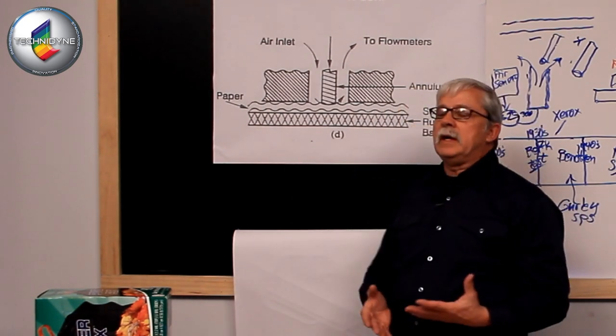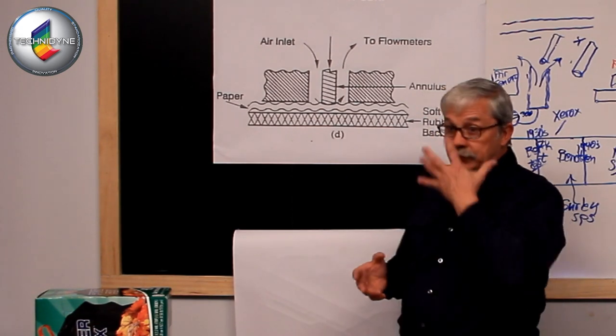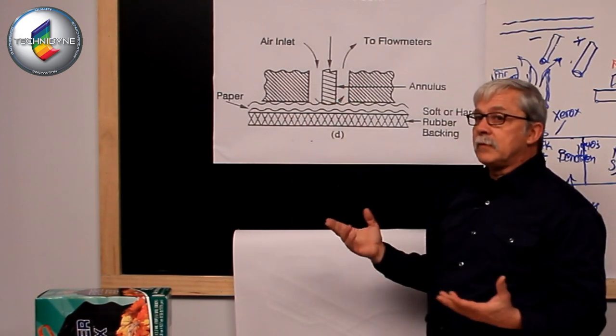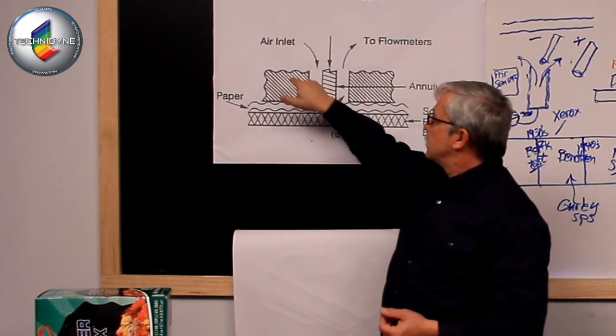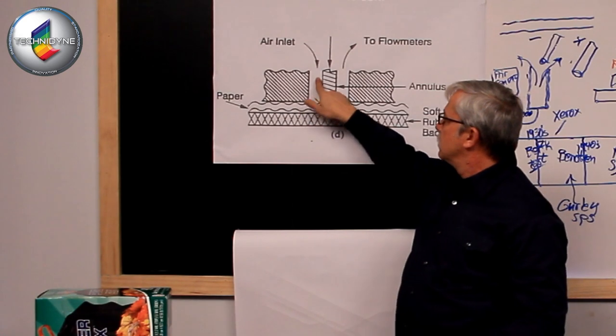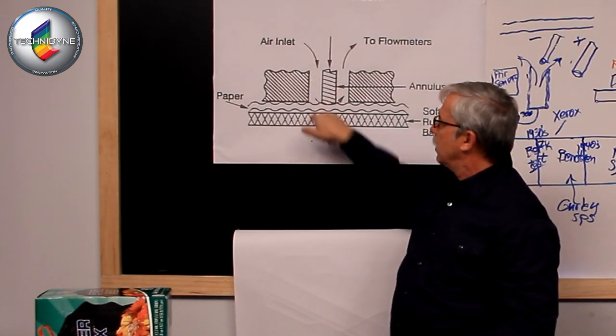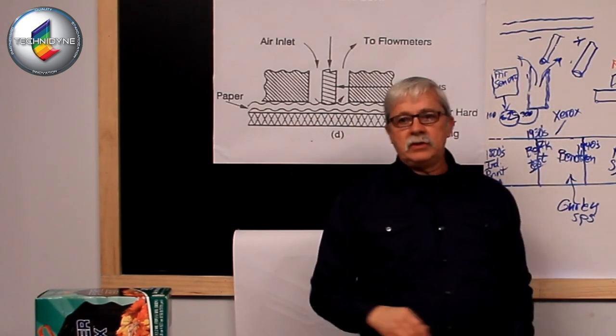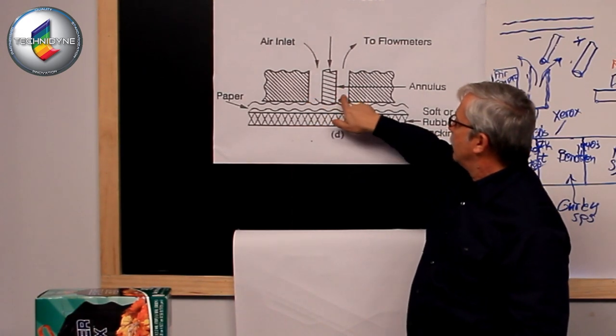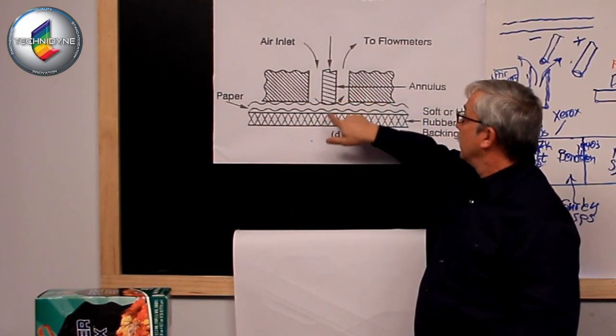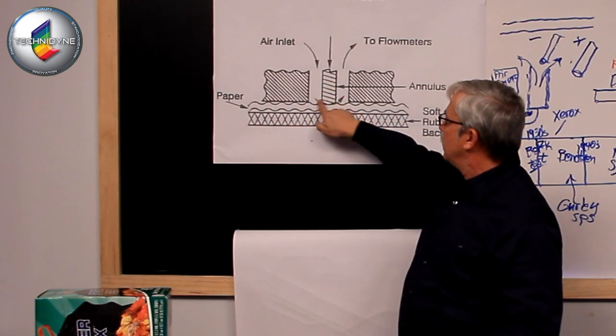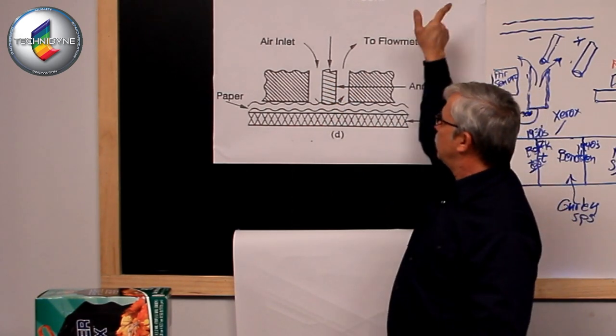And, again, he had to come up with some way of being able to produce some type of pressure differential from one side of this annular ring to the other in order to get some type of flow going through there. What he devised was a pathway, as we saw in the other picture, to enter. And so essentially, now we have this area here which we could consider our cylinder that we can charge with pressure. If we have a high pressure in this area, we have a low pressure in this area, comparatively speaking. Now the only path for that air to go and to equilibrate is underneath this metering land and across the topography of the sample and escape to atmosphere.